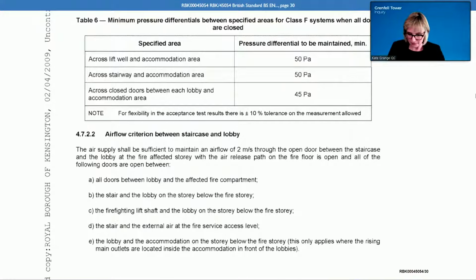I do, yeah. We're talking about AOVs here at the moment, though, aren't we? Yes. So it's got to be a smoke control damper. Can we agree on that? Yes, smoke control damper, yeah. And you're saying that you did in fact check the fire resistance of the dampers by looking at their product information. Is that right? Yeah. There is a section in the SCA guide that gives a range of different tests appropriate for a smoke control damper, and it followed one of those recommendations.